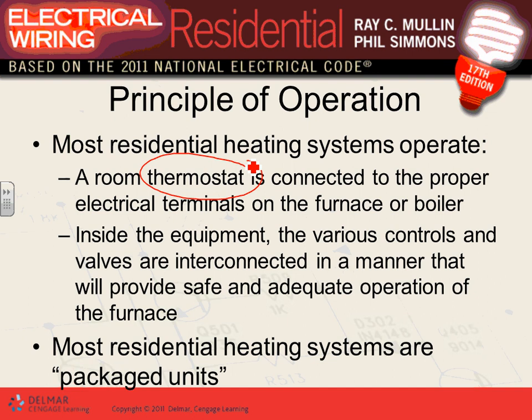You need a thermostat—a room thermostat—to regulate the temperature with upper and lower limits. Typically you place them on an interior wall. If you place a thermostat on an outside wall, the outside wall is always cooler, especially in Minnesota, and the thermostat won't sense the actual average temperature in your house.